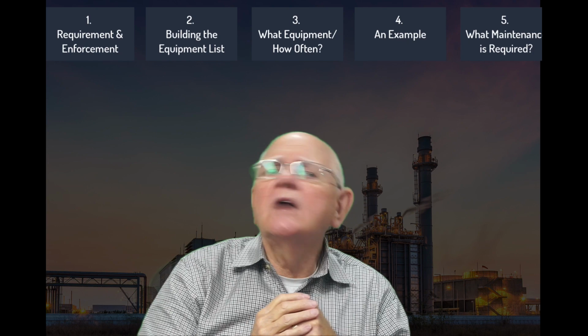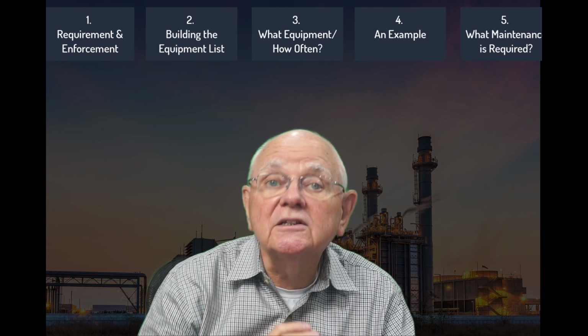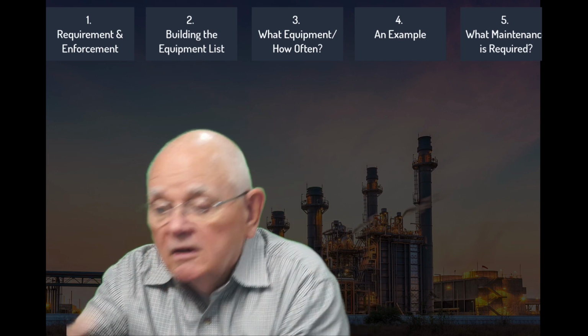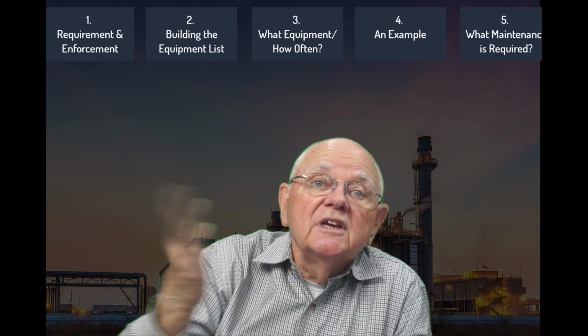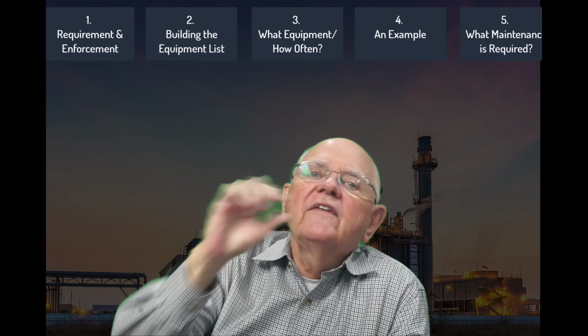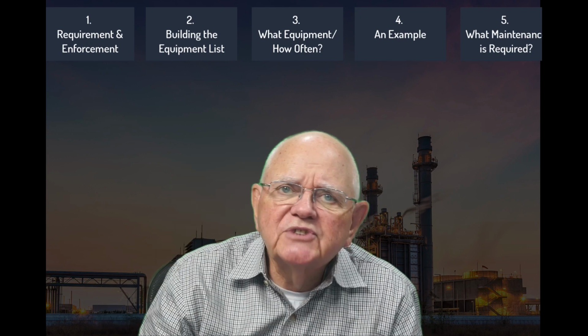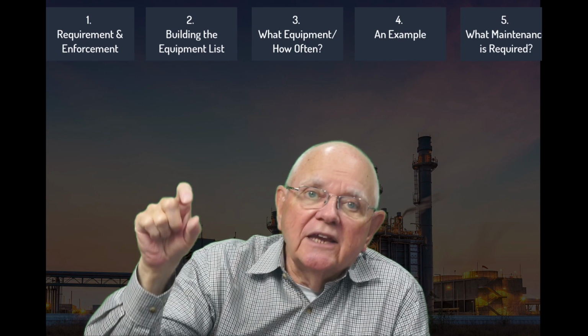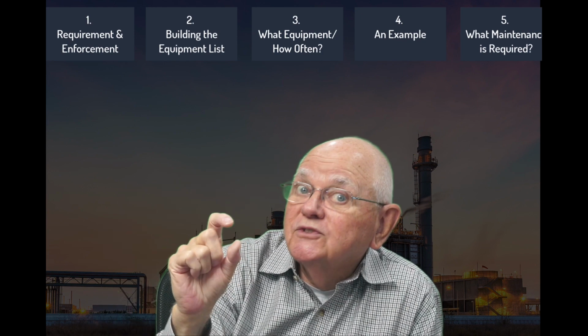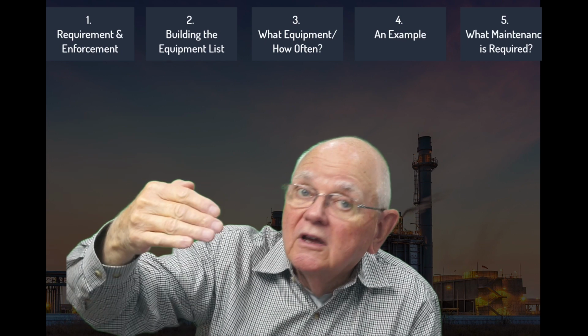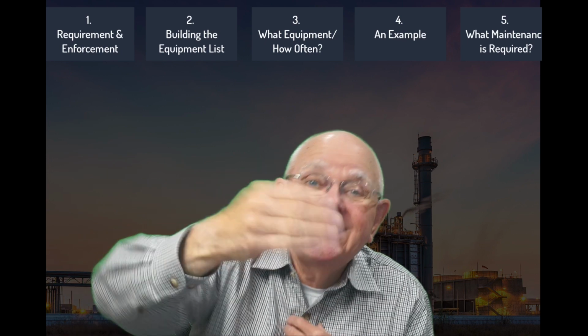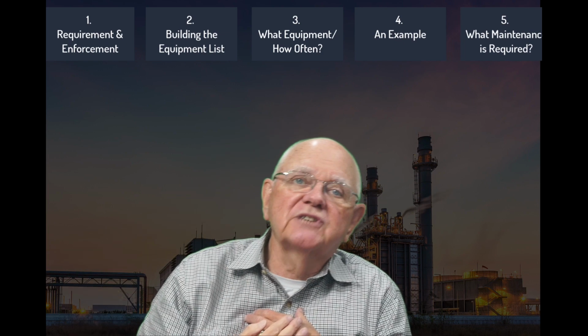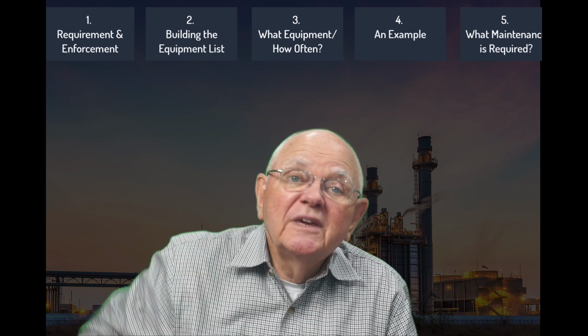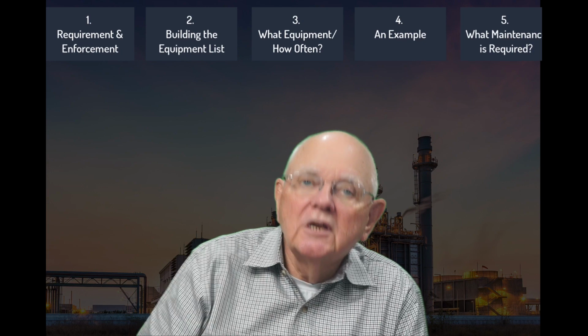I'm required by 70E, when I walk up to a piece of equipment, to determine its condition of maintenance. Has this motor or circuit breaker, whatever it is, been serviced in the last certain amount of time? Is its maintenance up to date? If there's a little label on that piece of equipment, disconnect, control panel or MCC bucket, that says next service due date, and I fall before that date, say it's 6 months from now, I know my equipment has been maintained. If I'm past that next service due date, we did miss that maintenance schedule, and so it may no longer meet the requirements for a proper condition of maintenance before I perform normal operation and servicing on that equipment. So keep those little service labels in mind.